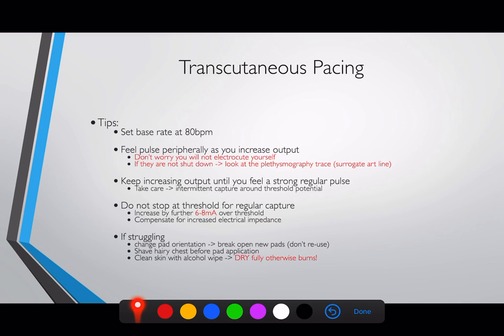Then increase the output by another 6 to 8 milliamps above the threshold you noted. This compensates for increased electrical impedance — shocking through tissues 80 times per minute means the impedance can increase, muscles can lose electrolytes, and transmission of electricity can reduce. The threshold to trigger a mechanical beat may therefore rise over time. This is also important when patients are being moved, as thoracic impedance may change.